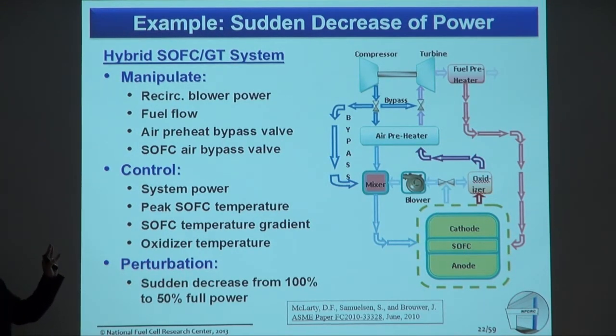In this particular case, we can manipulate certain variables to control this system under dynamic operating conditions: the recirculation blower power, the fuel flow rate, and the air preheat bypass valve. This bypass valve lets me either preheat the air or bypass it directly to the mixer. And there's the solid oxide fuel cell bypass valve, where I can either send the gas recirculated here or send it directly to the turbine.